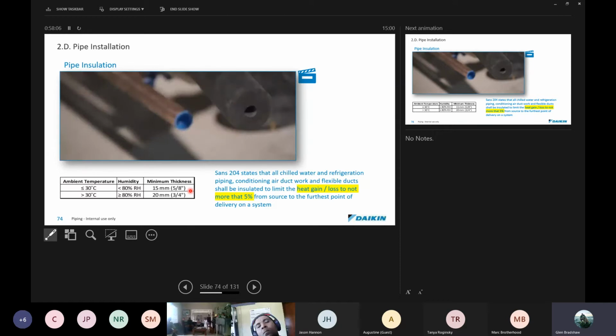All right, the next thing, something that we've been pushing a bit in recent times, is pipe insulation, and it's marked in our installation manuals. You'll see that, for instance, if you live in a climate less than or equal to 30 degrees and less than 80% RH, you can use a 5/8 pipe according to the Daikin spec. If you're in an environment with greater than 30 degrees or greater than 80% RH, average temperatures, then you should be using 3/4. Cape Town falls in the region of 3/4. In fact, I think most of South Africa, by the Daikin spec, falls in 3/4.